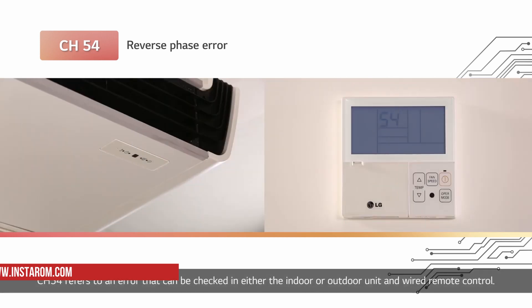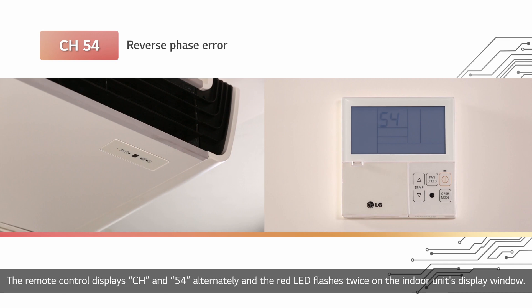CH 54 refers to an error that can be checked in either the indoor or outdoor unit and wired remote control. The remote control displays CH and 54 alternately, and the red LED flashes twice on the indoor unit's display window.